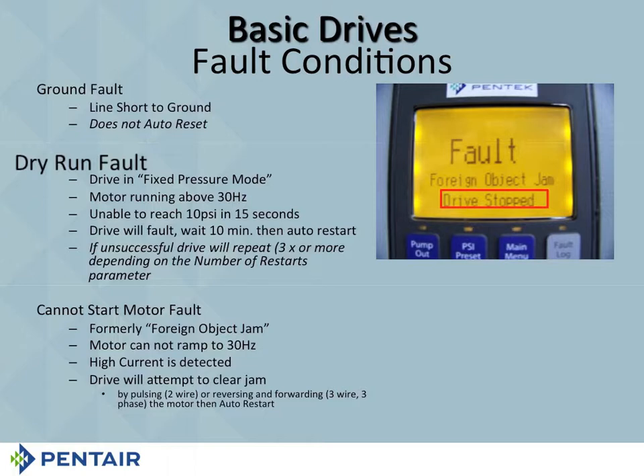If it can't put the pump to sleep, it'll fault again. Now, if it faults a third time, then it goes into drive stopped. But the first 2 times that it faults, it'll say restart pending. You can wait 10 minutes, or you can push the reset button and hope that you got enough water to get the thing to go to sleep. All of that is adjustable. The 10 psi is adjustable. The 15 seconds is adjustable. The 10-minute wait is adjustable. The number of times I restart, that's all adjustable.